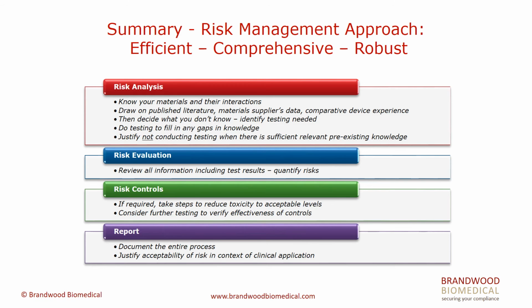What testing do you need to add? You do the testing to fill in any gaps in the knowledge, and you can justify not conducting testing where there is sufficient relevant pre-existing knowledge. Evaluate the whole thing, that's the risk evaluation step, including any test results, quantify the risks, introduce any risk controls you need to do, and then report.